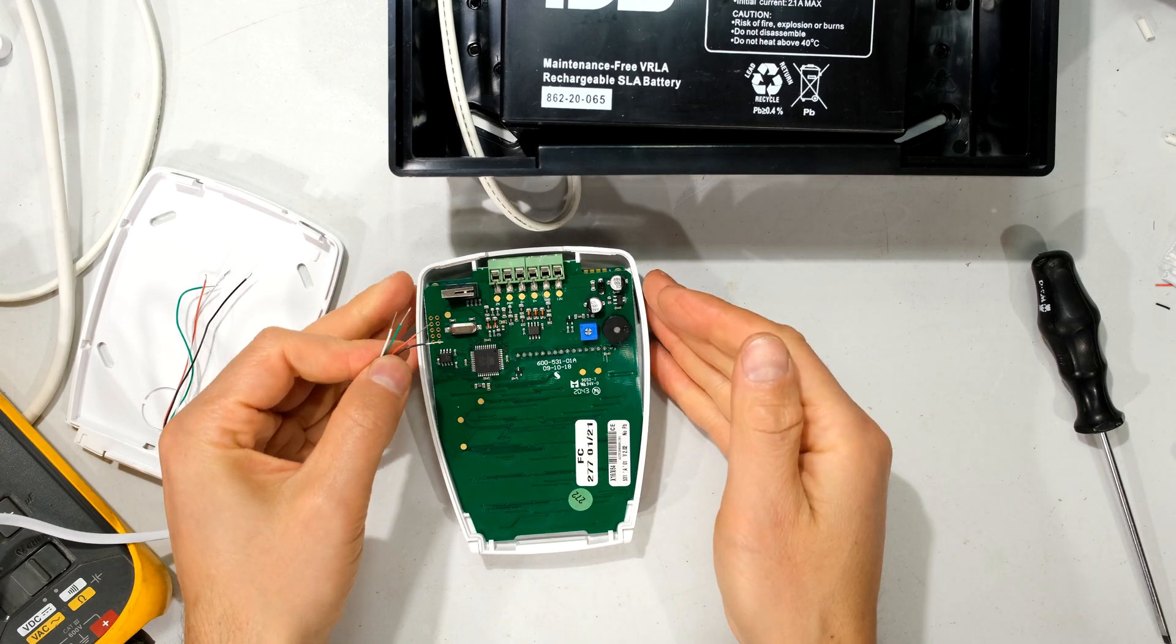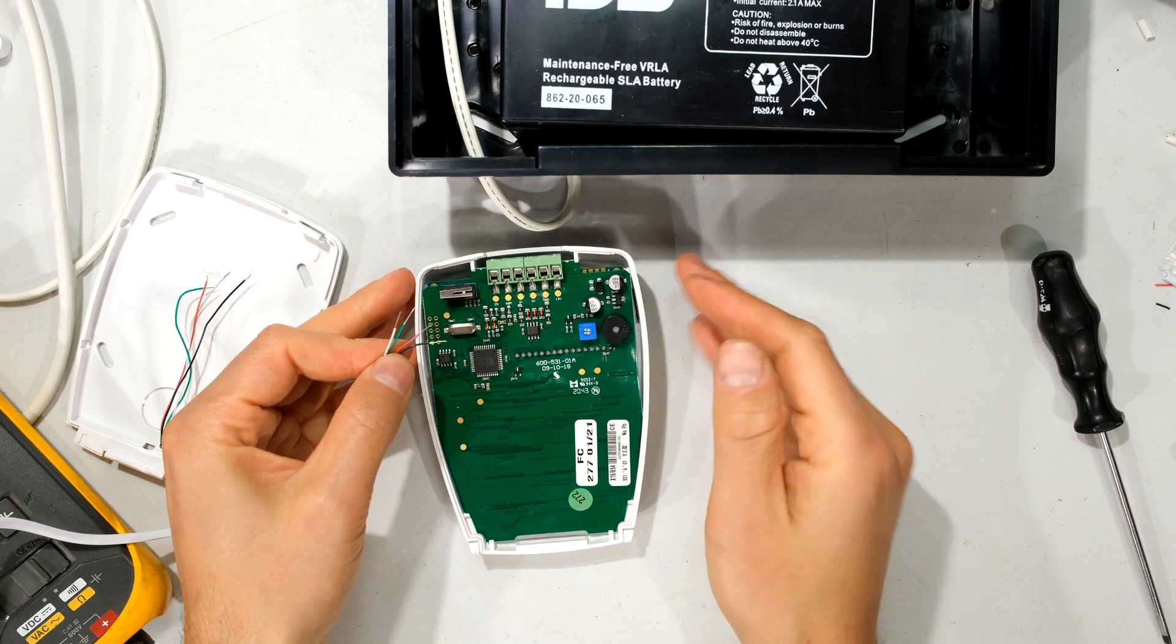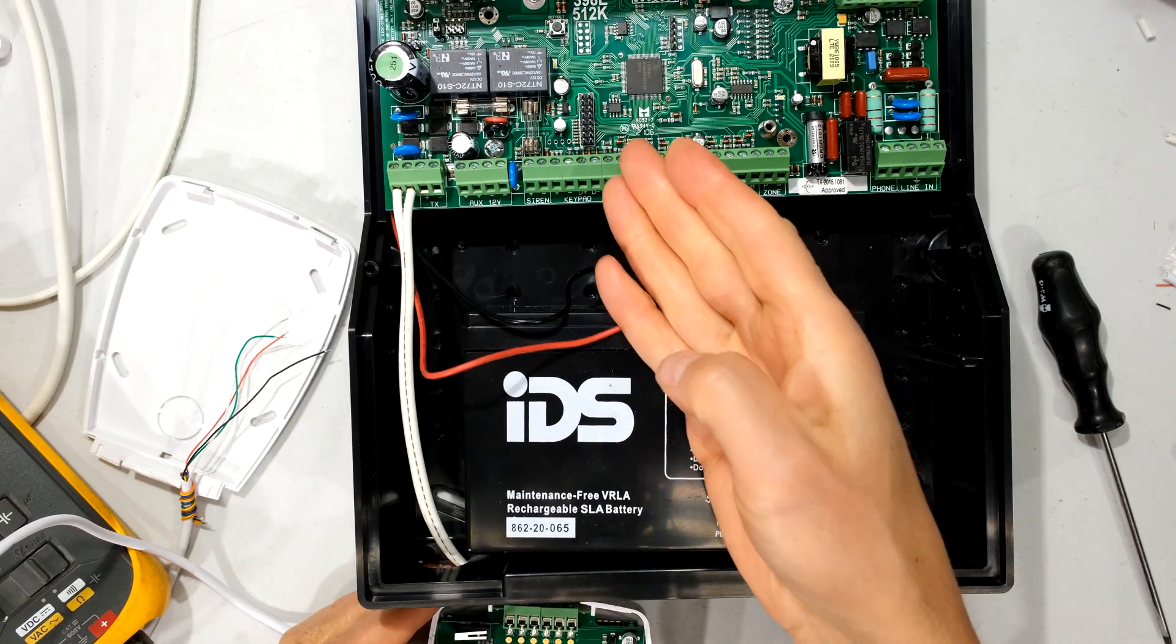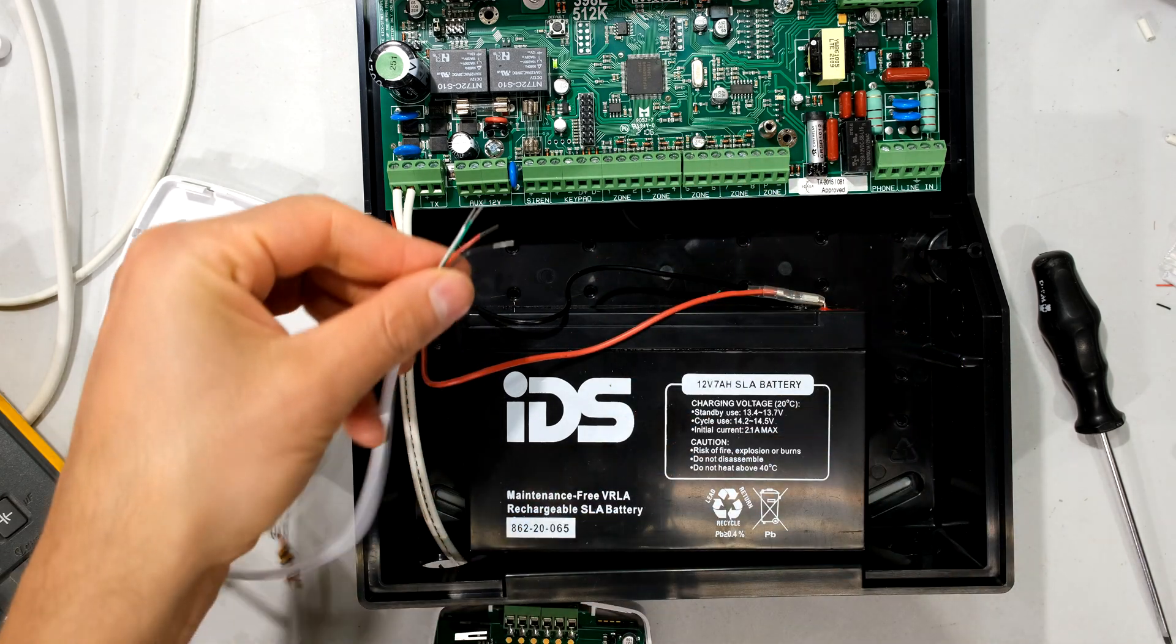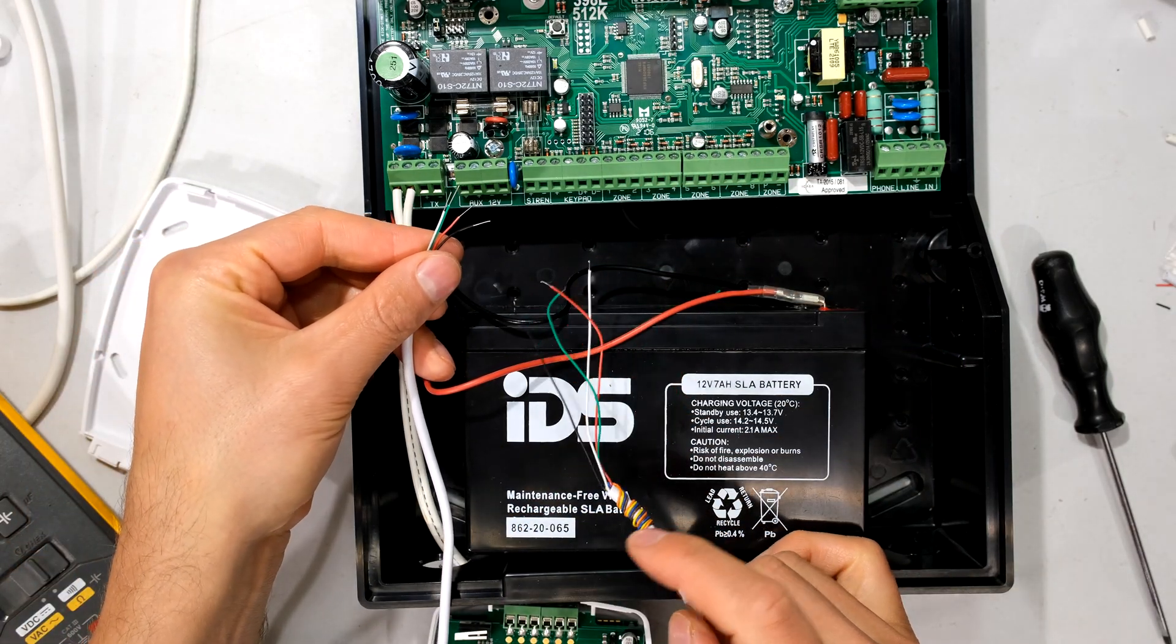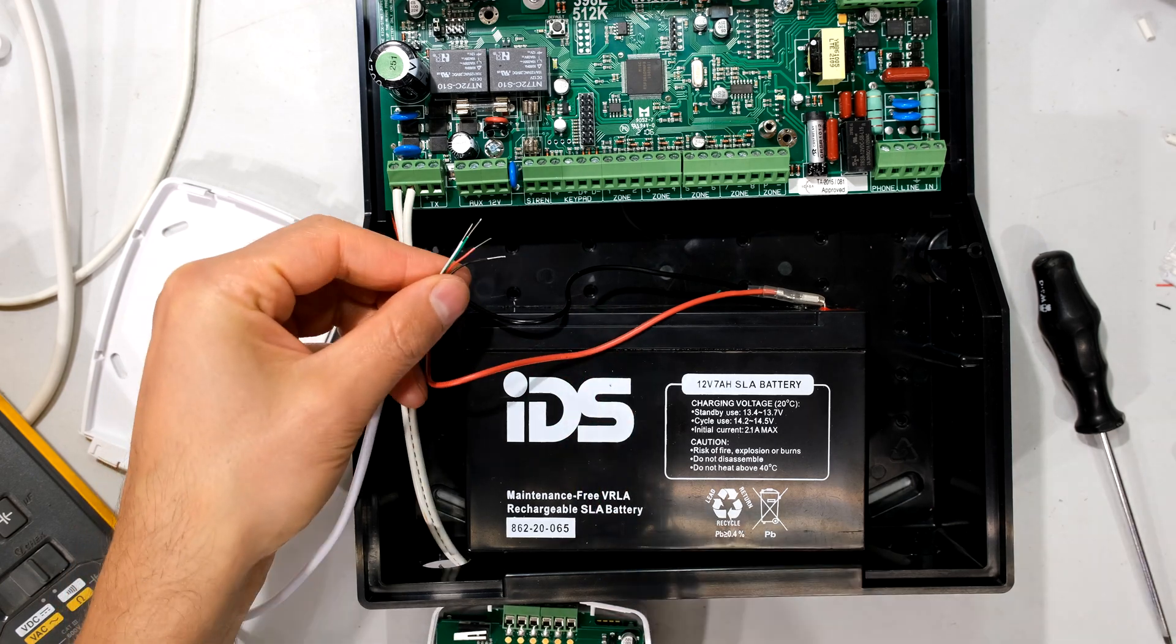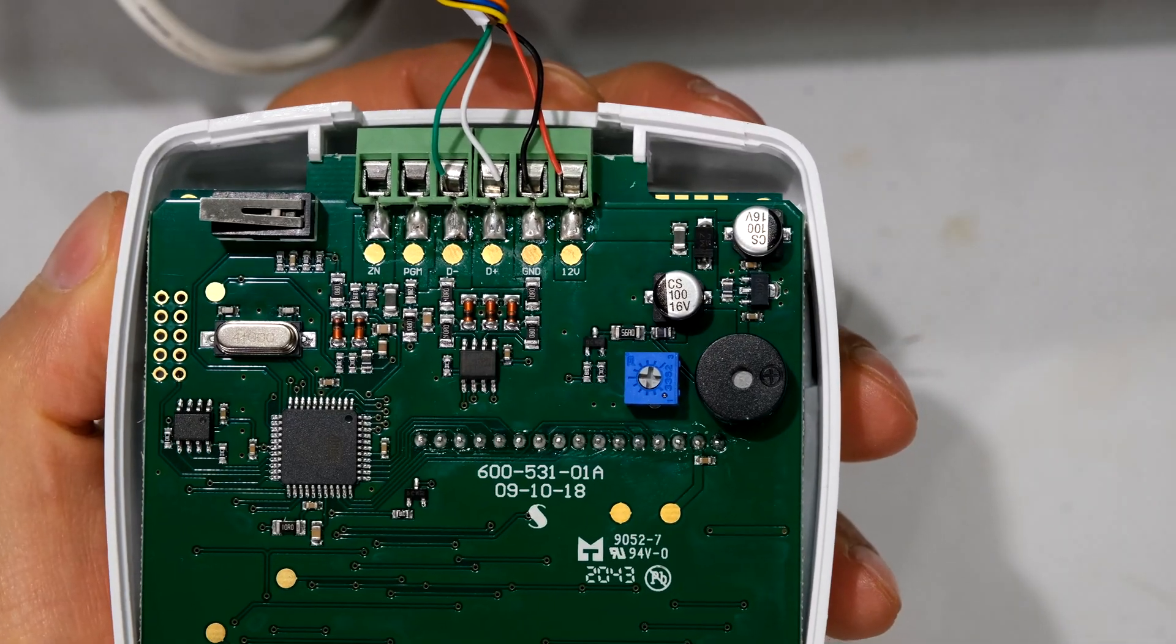Now I prefer to wire the keypad first. Reason being, is if you start here and the panel is energized, you might find that you are shorting out the leads while you are doing your cabling or while you're doing your connections.